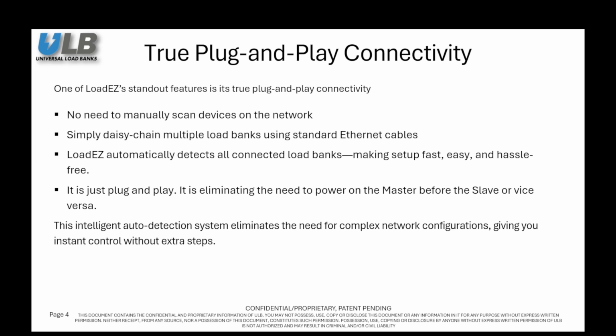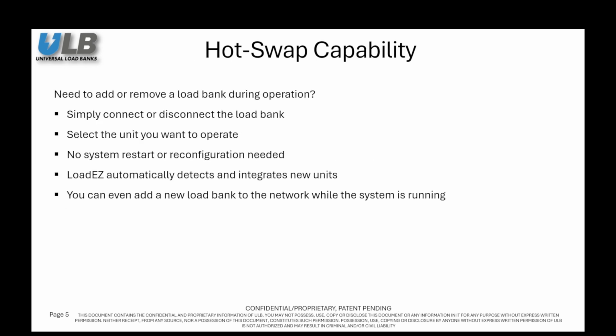It eliminates the need to power on the master before the slave, or vice versa. This intelligent auto-detection system eliminates the need for complex network configurations, giving you instant control without extra steps. LoadEZ also supports hot swap capability, designed for uninterrupted operation. If you need to add or remove a load bank during operation, it's simple. Just connect or disconnect the unit and select the one you want to operate. There's no need to restart the system or reconfigure anything. LoadEZ will automatically detect and integrate any new load bank you connect, even while the system is running.